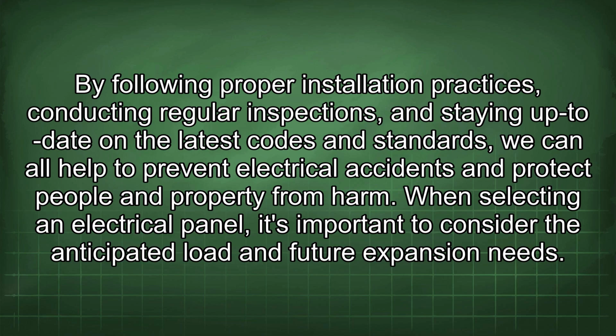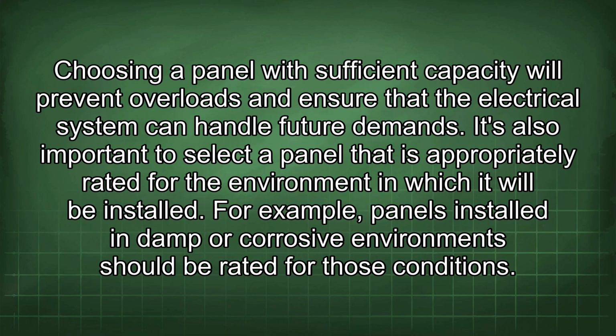When selecting an electrical panel, it's important to consider the anticipated load and future expansion needs. Choosing a panel with sufficient capacity will prevent overloads and ensure that the electrical system can handle future demands. It's also important to select a panel that is appropriately rated for the environment in which it will be installed. For example, panels installed in damp or corrosive environments should be rated for those conditions.